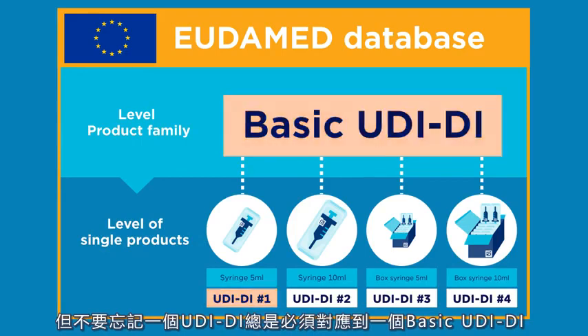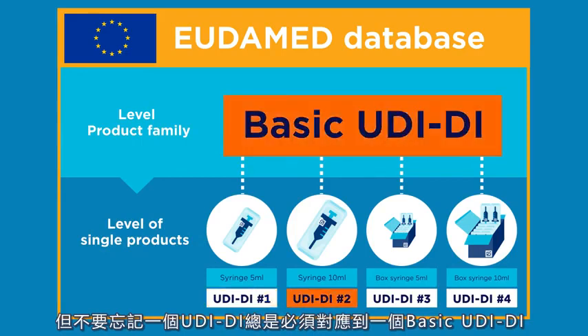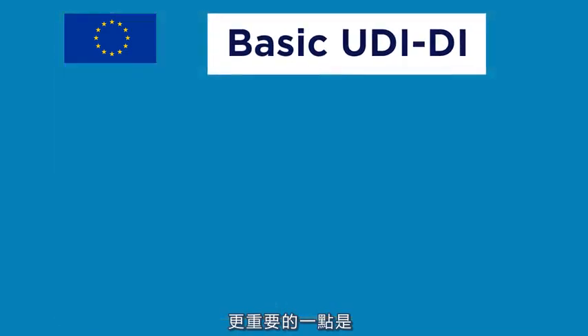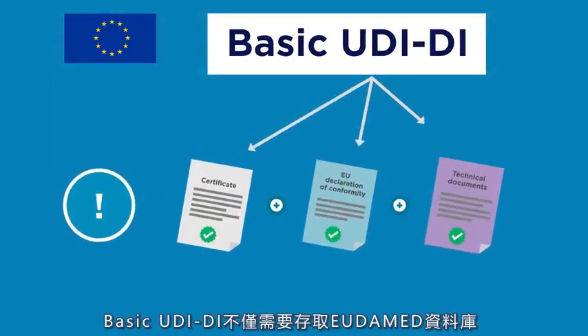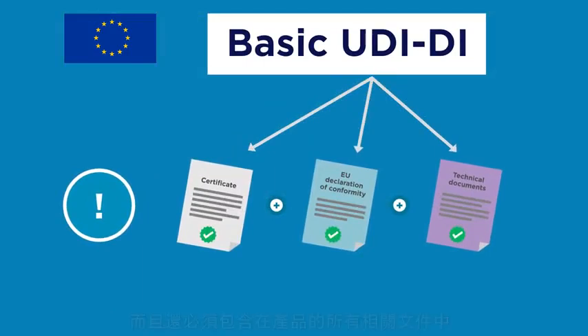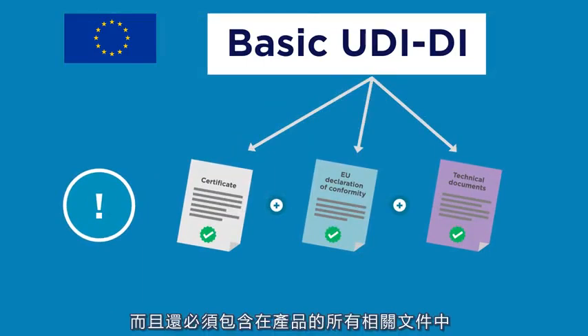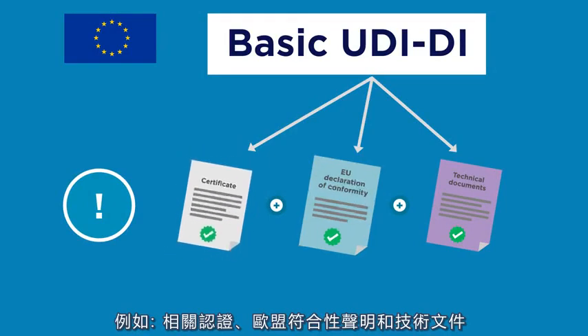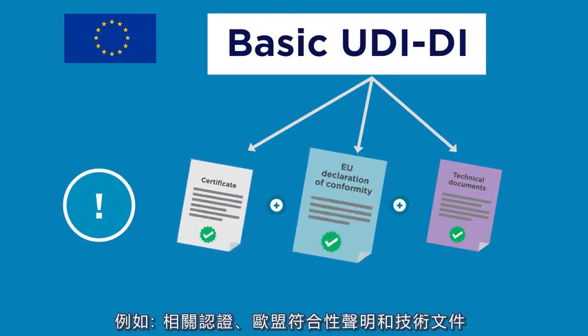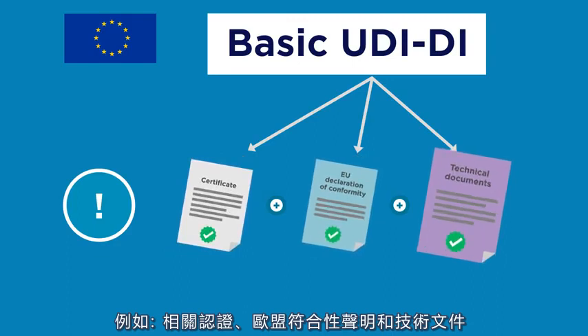A UDI-DI must always be linked to only one basic UDI-DI. The basic UDI-DI is not only required to access the EUDAMED database — it must also be included in all relevant documents for the products, for example certificates, EU declarations of conformity, and technical documentation.